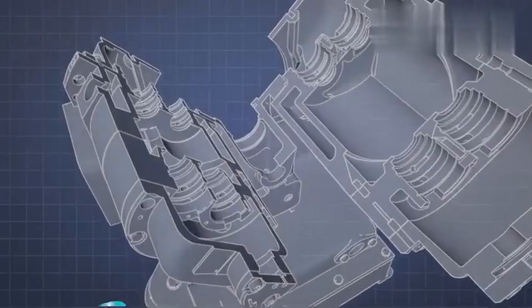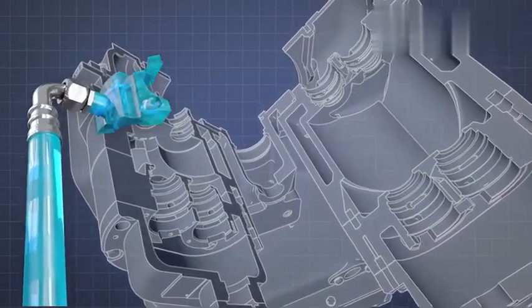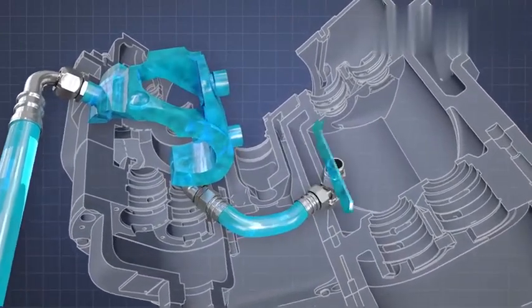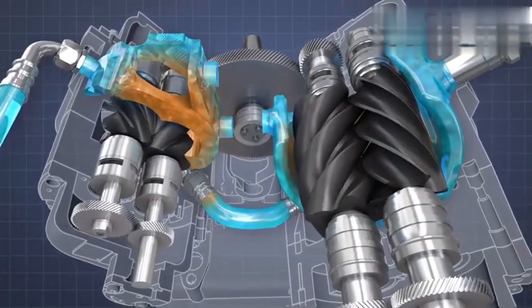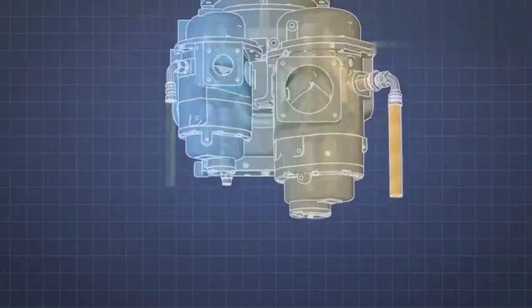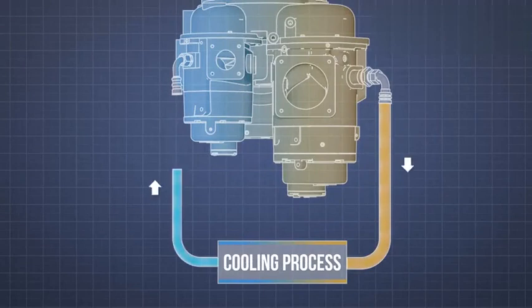The compression process is kept cool by a constant flow of water pulsing through channels that surround the air end rotors. Heat transfers to the water which is then pumped through an external cooler before returning to the air end.